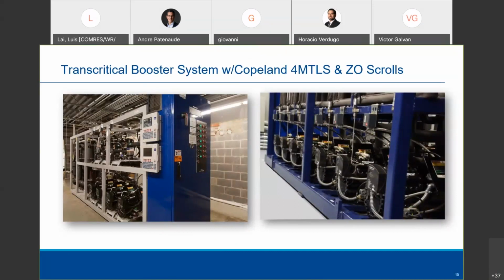The one on the right has 7 transcritical compressors. And I was actually in a store where they had 11 on a single rack, 11 4 MTL 15s, so 150,000 BTU nominal capacities, 11 of them, and 4 subcritical scrolls on a rack. So these racks can get fairly large, depending on where you are and depending on the horsepower allowable in whatever region that you're in.